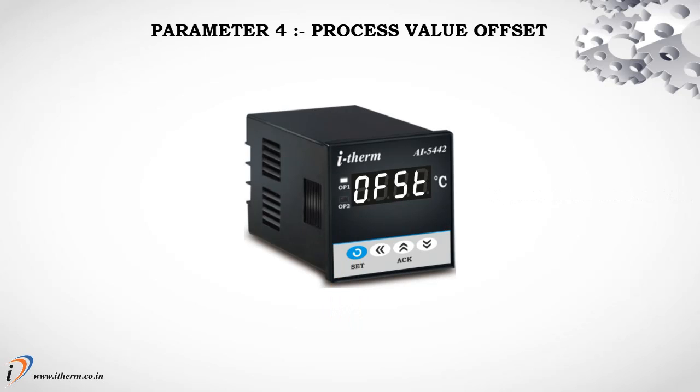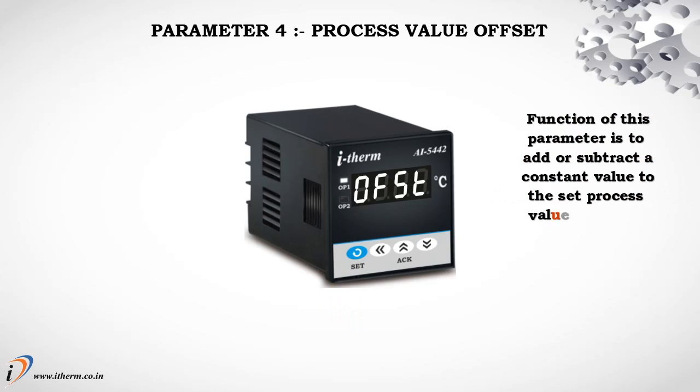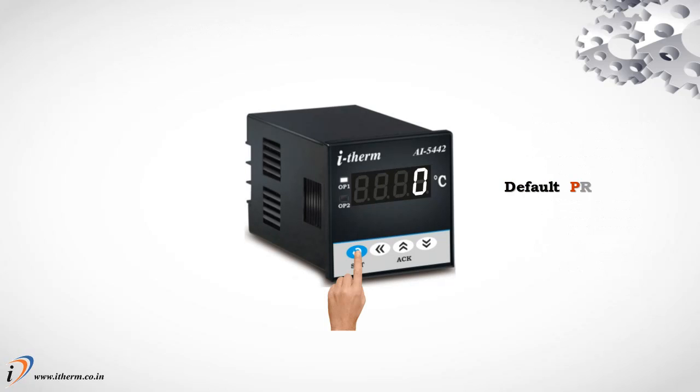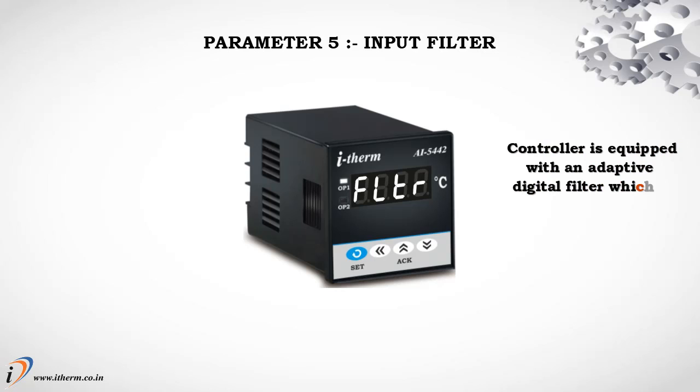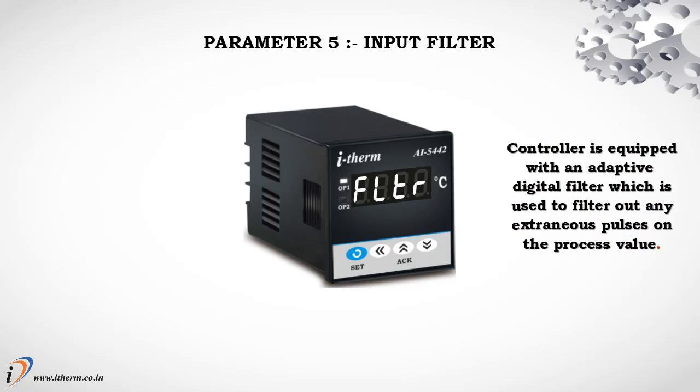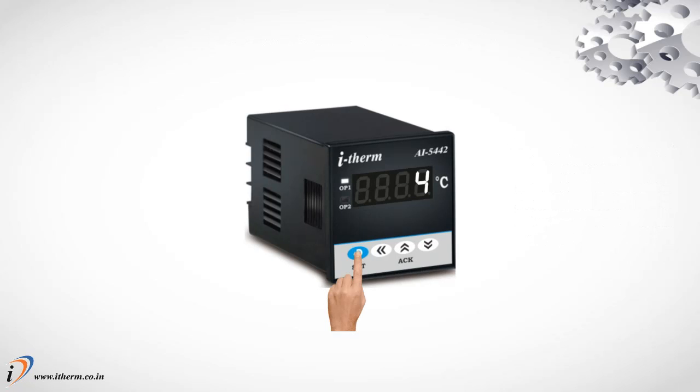Parameter 4. Process value offset. Function of this parameter is to add or subtract a constant value to the set process value to obtain final process value for control application. Default process offset value is 0. Parameter 5. Input filter. Controller is equipped with an adaptive digital filter which is used to filter out any extraneous pulses on the process value. Default input filter value is 4.